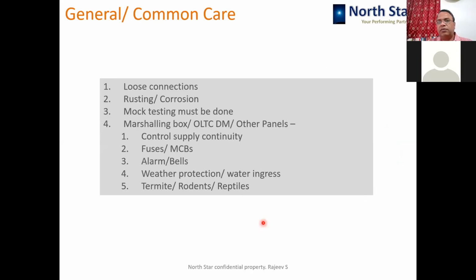Okay, so general common care, if you look at it from the component point of view, is loose connections, rusting, corrosion. It is likely to happen to your enclosures, your boxes, marshalling boxes, OLTC boxes, panels. They are likely to get rusted. So anti-rust sprays or painting is required to be done. Mock test to be done of all the protection devices.